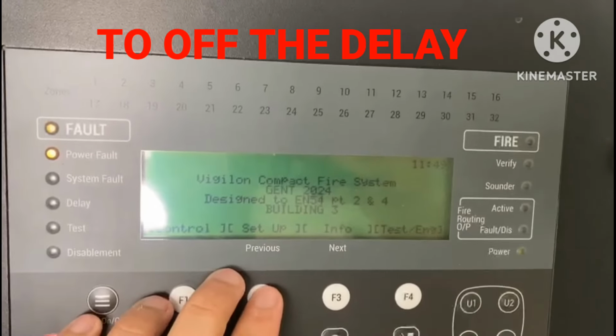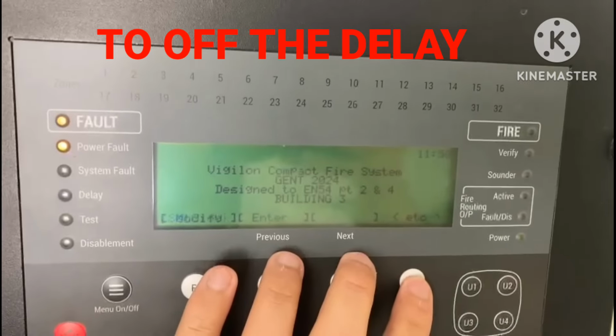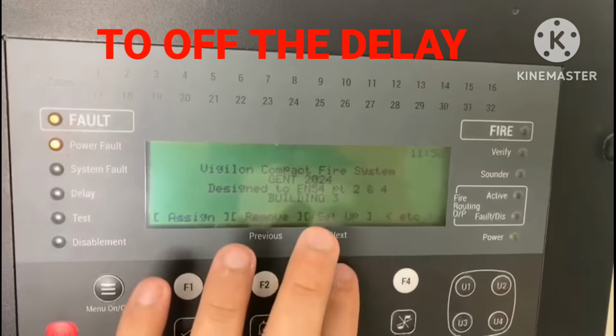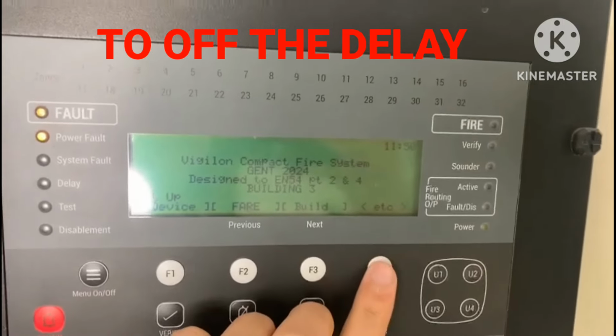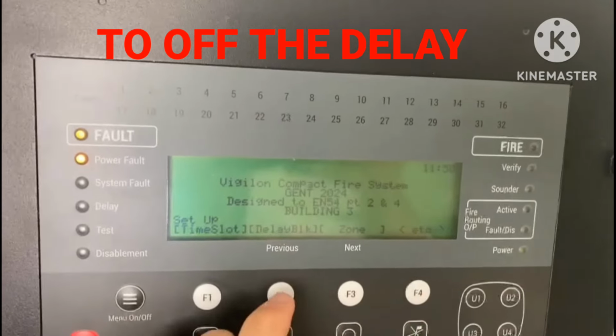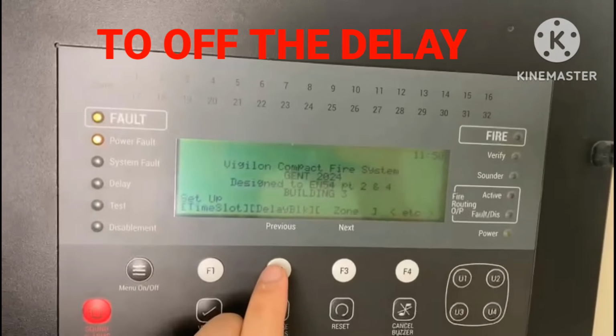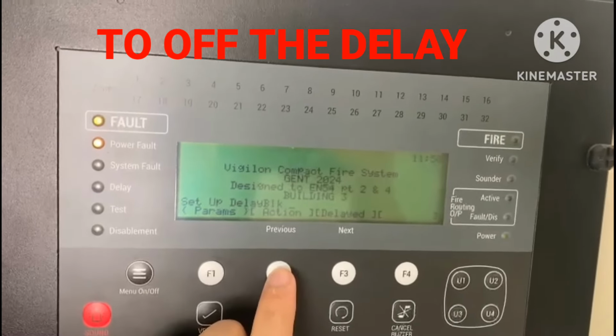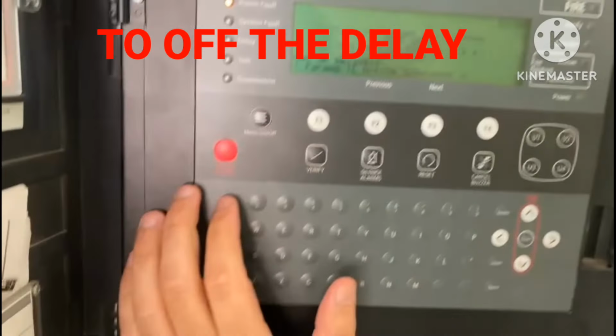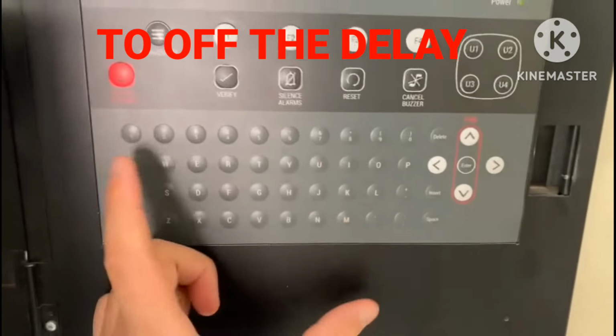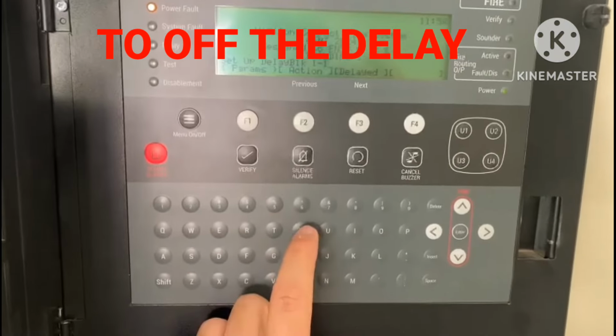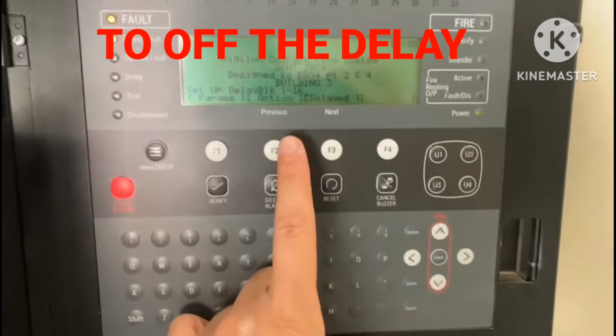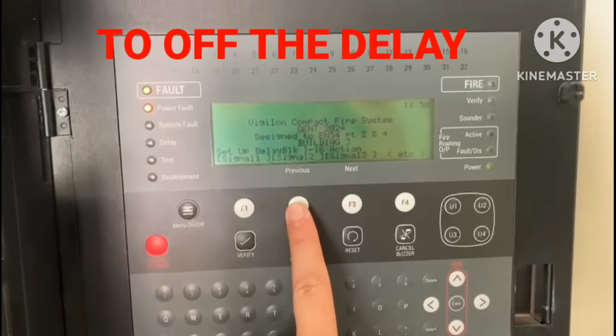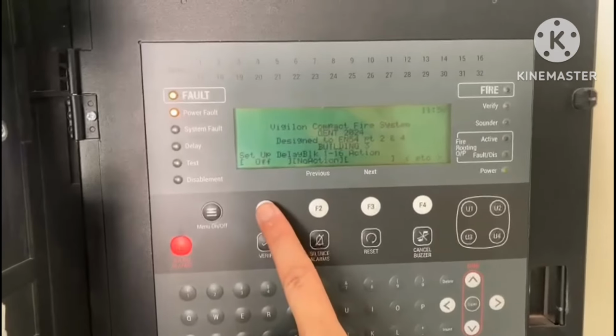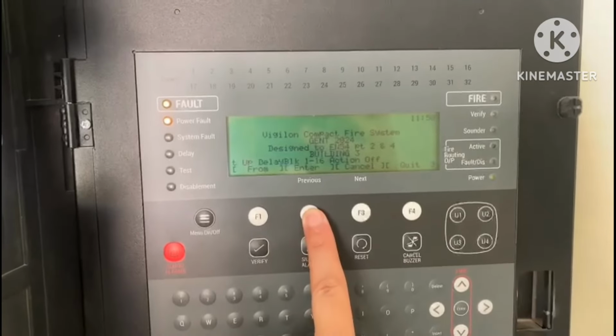To turn off the delay LED, we will go to menu, setup, then setup, then delay block, F2 delay block, then we will put the delay block number for which the delay is on. If you don't know, you can put from 1 to 16 as the delay block number. Then action. For the action here, we have two options of the enter.